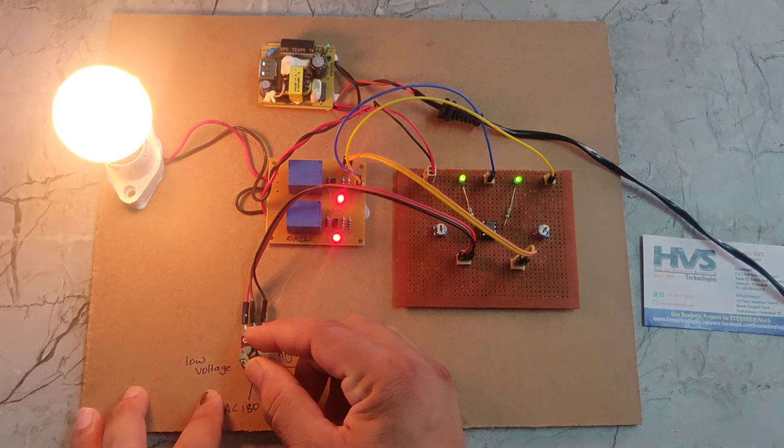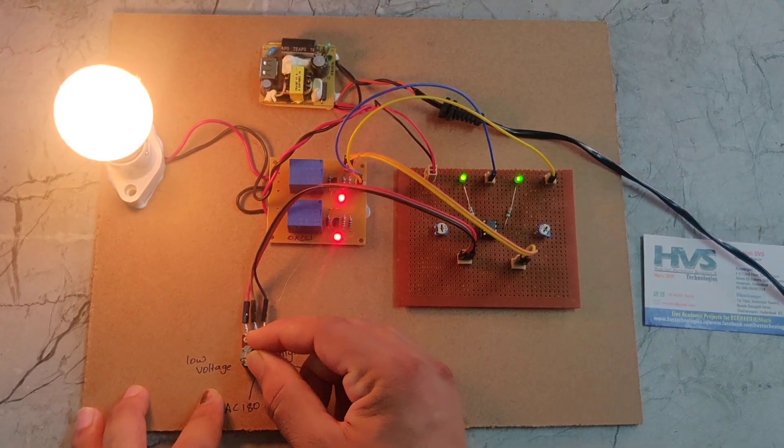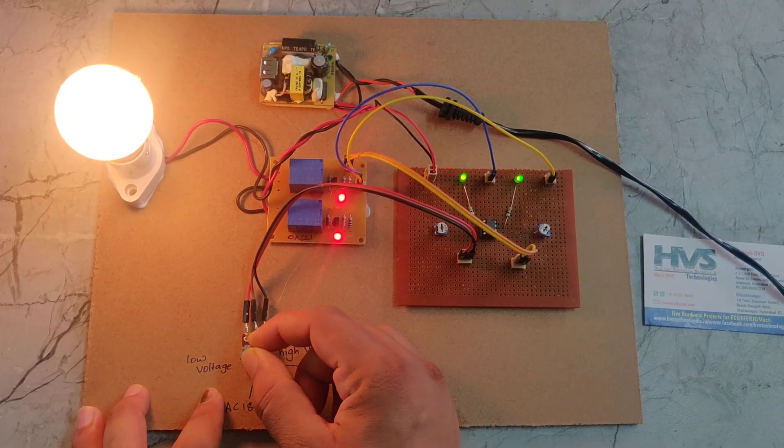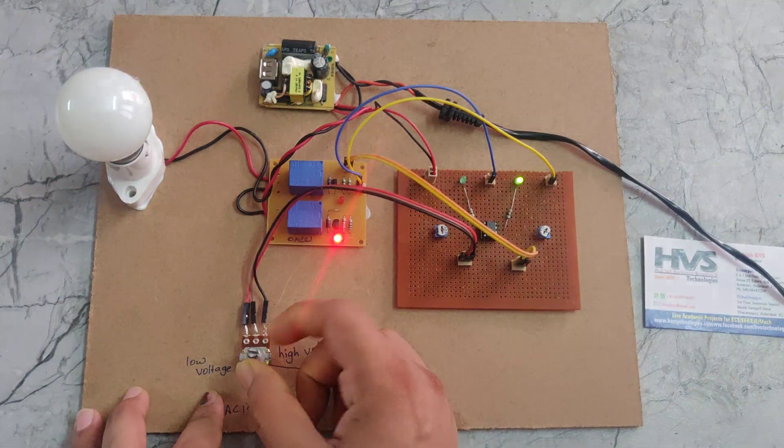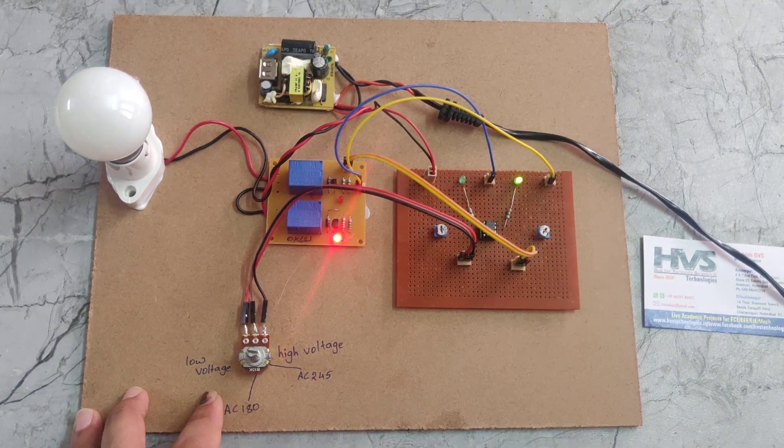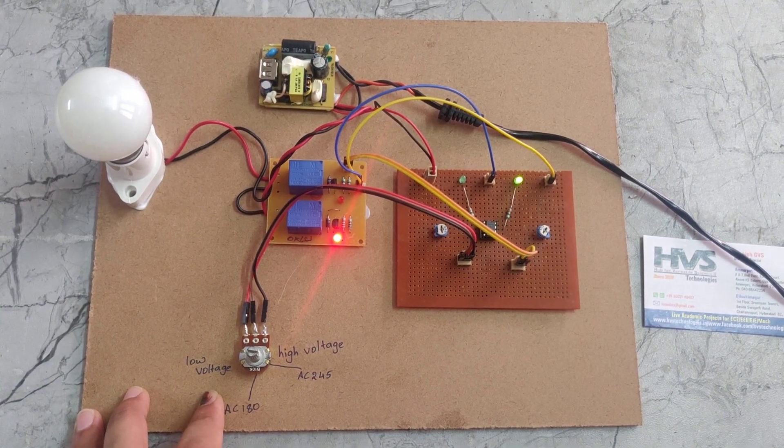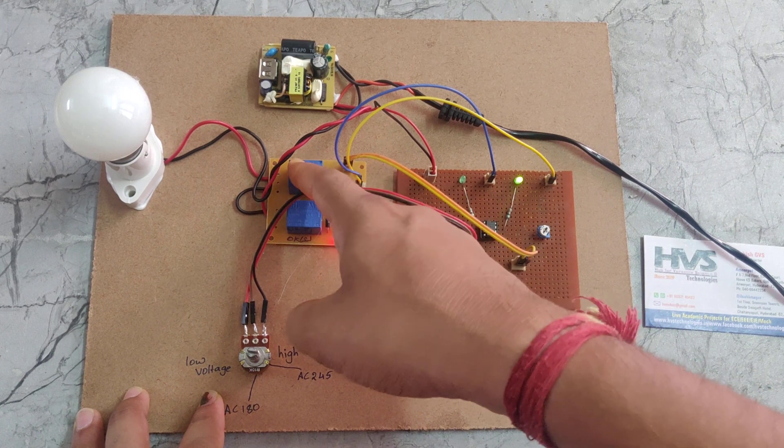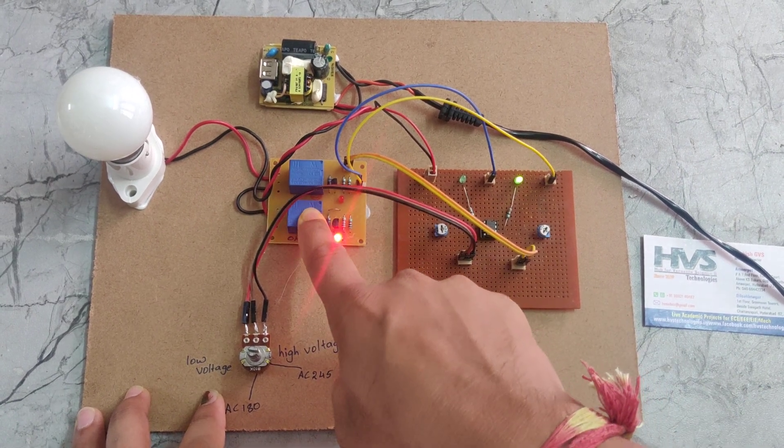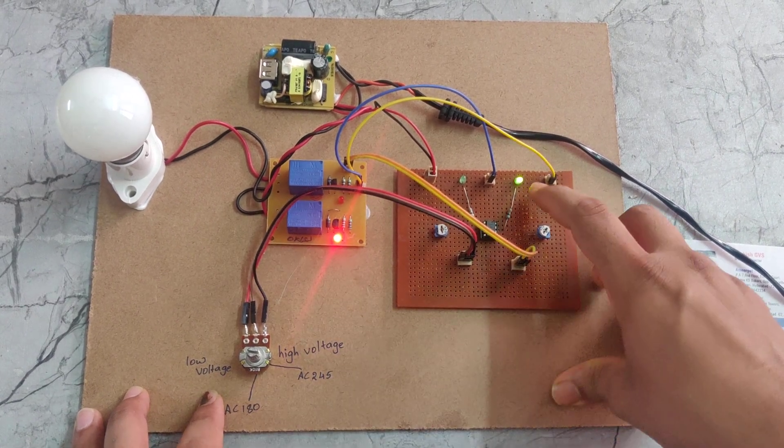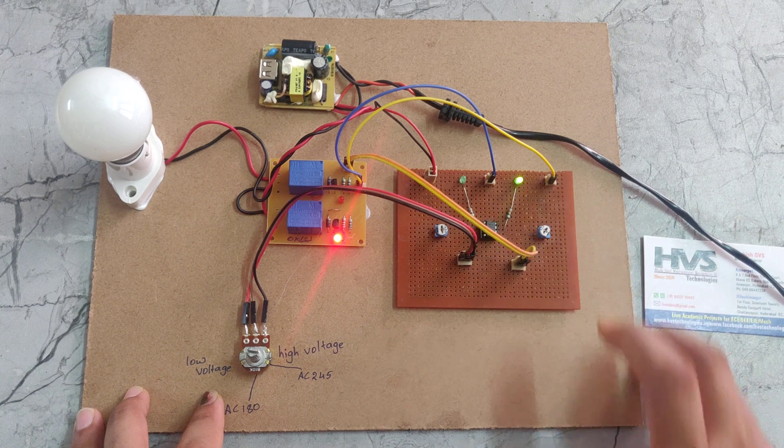If I increase to normal voltage, it's in normal position. If I increase above 245V, this relay will switch off and this relay stays on, and we can see another light indication there.